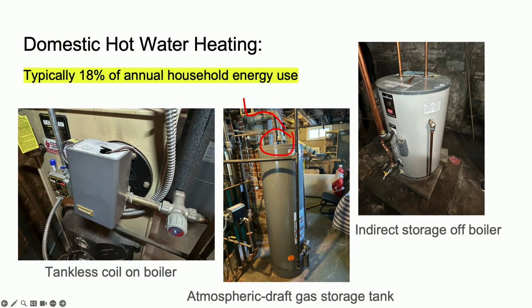This is really easy to backdraft. So if people at the house are turning on all the exhaust fans in the bathroom, running the clothes dryer, and you've got that jet engine 400 CFM kitchen exhaust fan, it can definitely start pulling the exhaust gases back into the house, and then you're just breathing carbon monoxide. So you don't see these very much anymore.